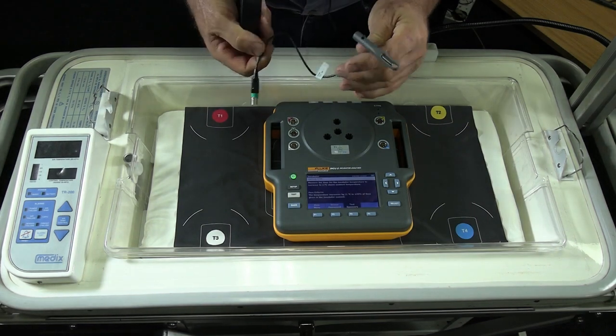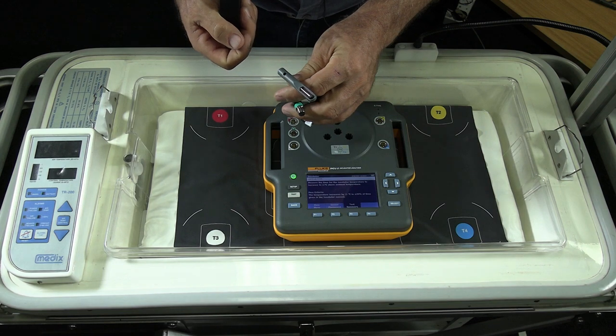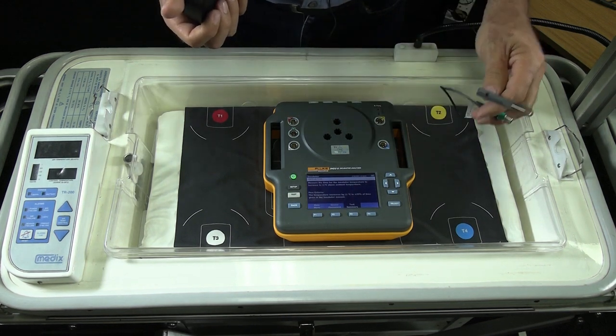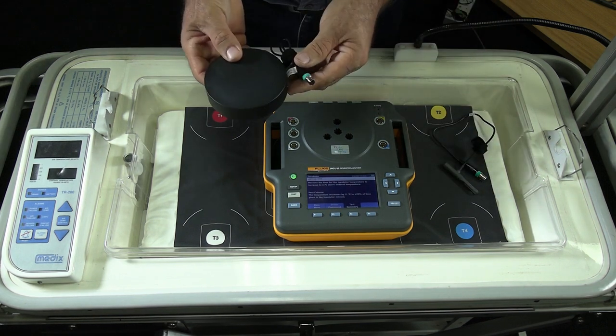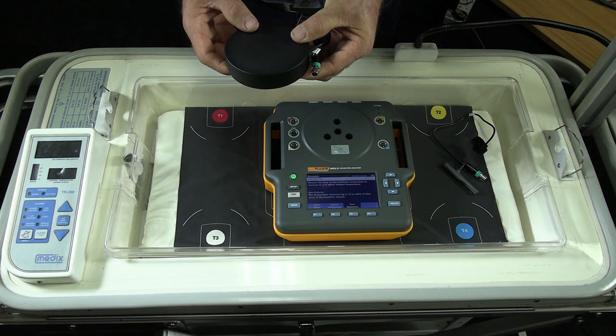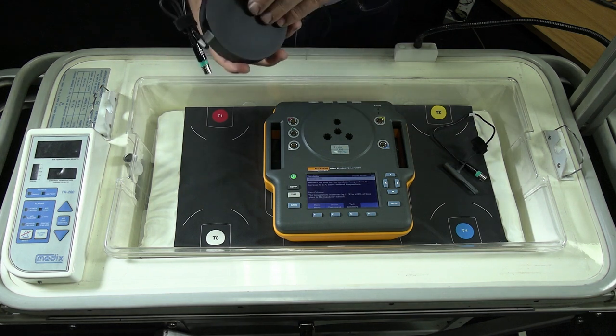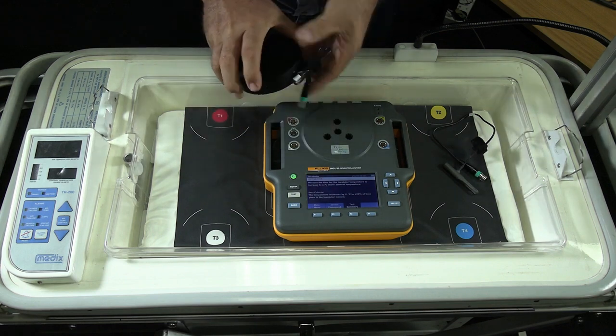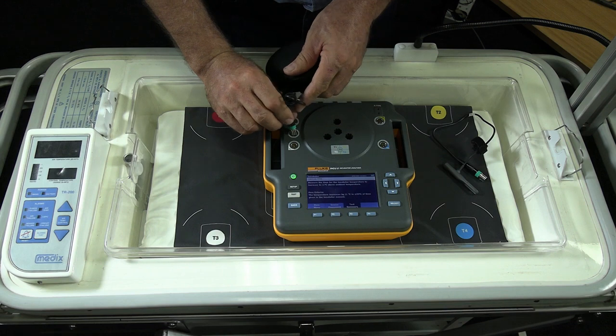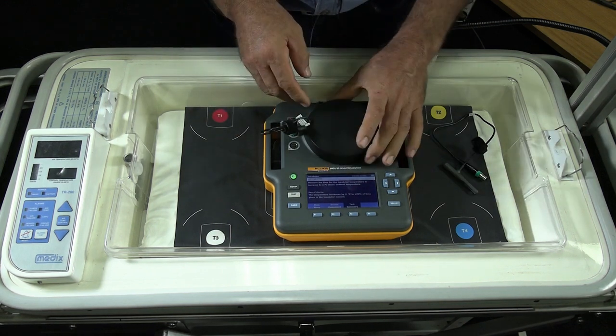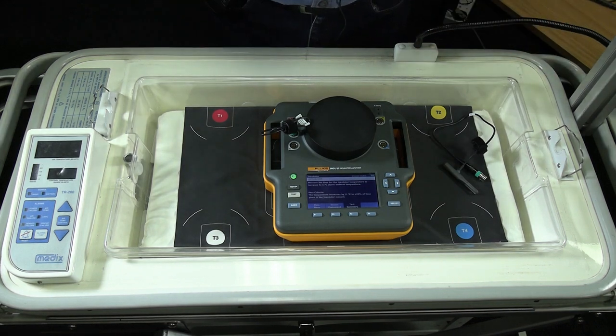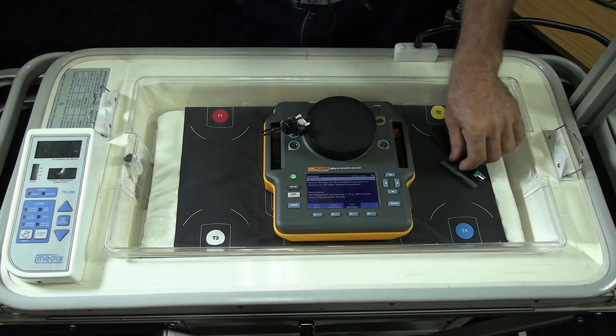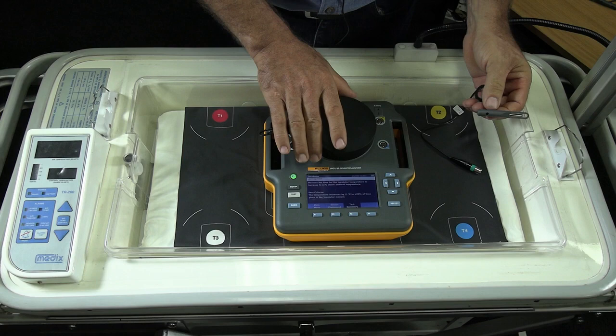Those are your temperature probes. Now, when we do measure incubators, we make use of these smaller temperature sensors. But when we're going to do an overhead warmer, we're making use of different sensors. You'll see that in your kit, you have a separate bag with 5 of these metal discs. So what will happen is you will place these in the same spots, color-coded as the previous ones, and your overhead lights will now heat up this plug. And then once that plug reaches stable temperature, you'll get your measurements from it. So for incubators and transport incubators, we use these temperature sensors, and for overhead warmers, we make use of these plugs.